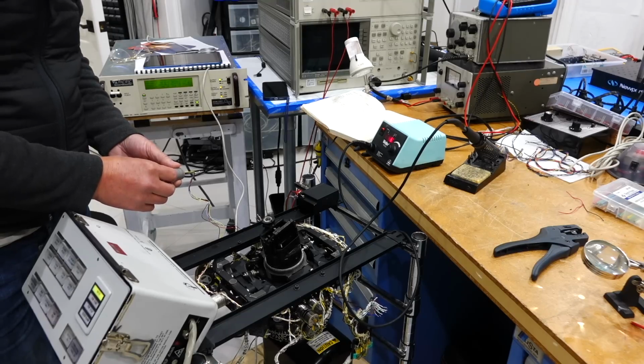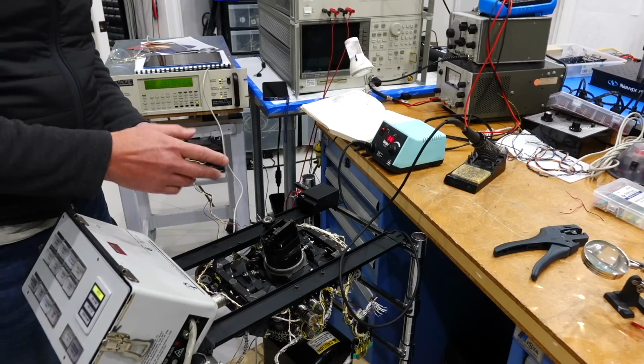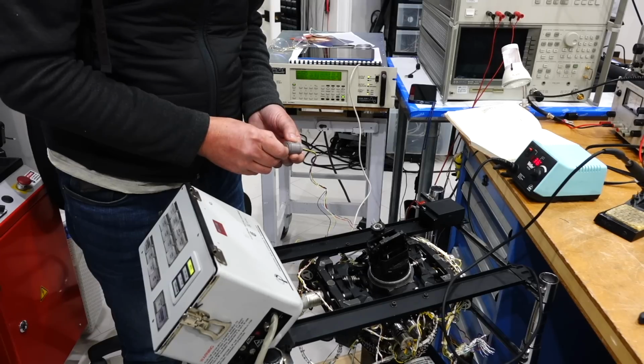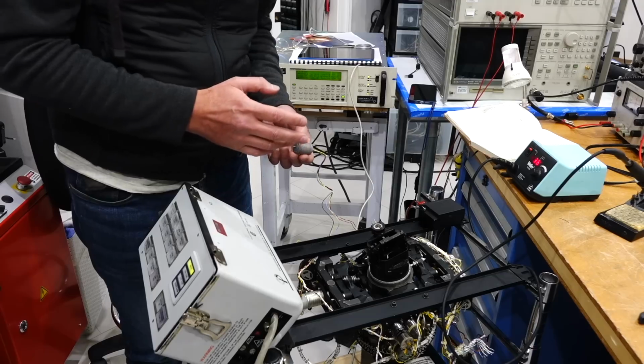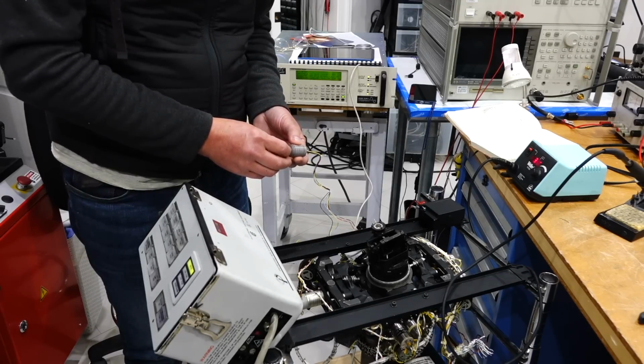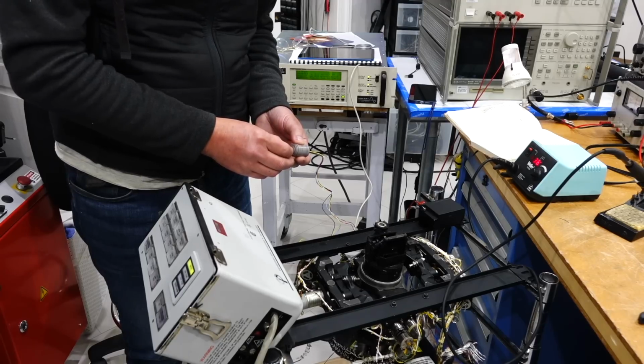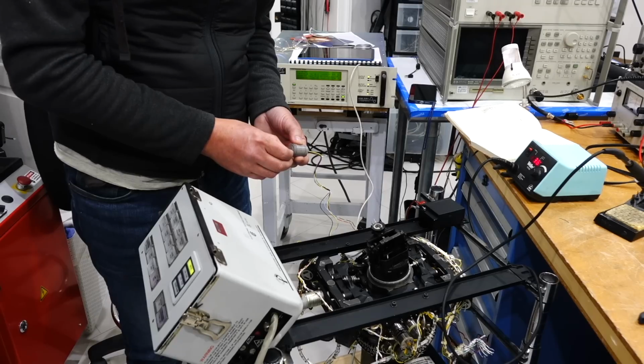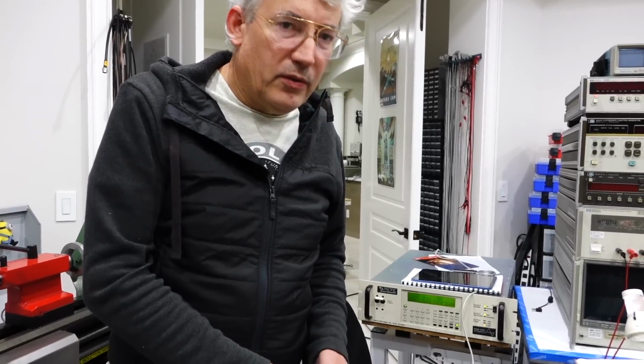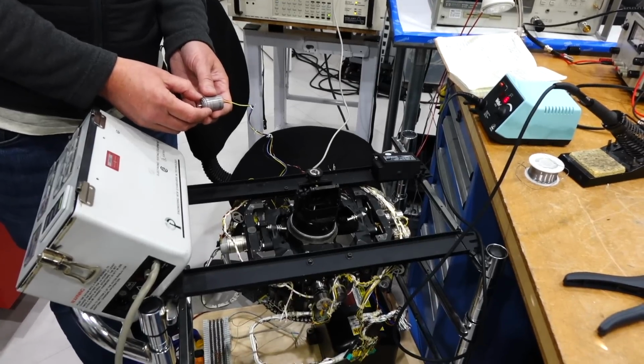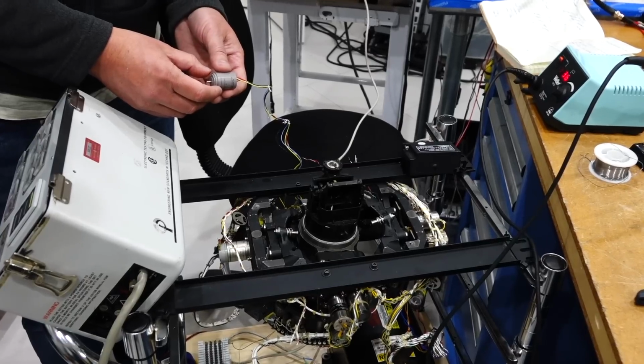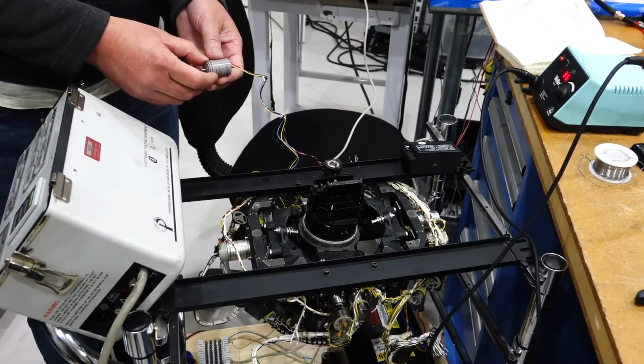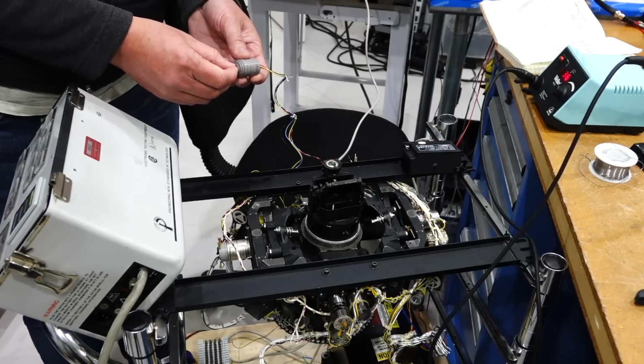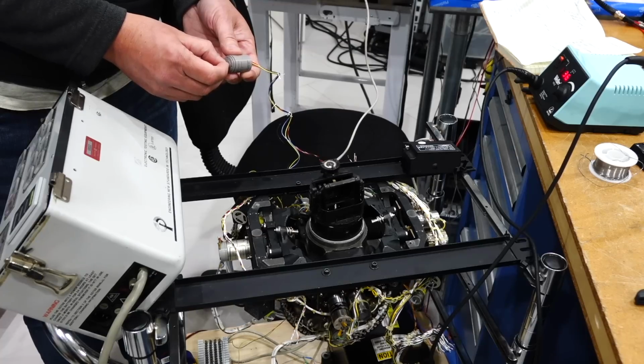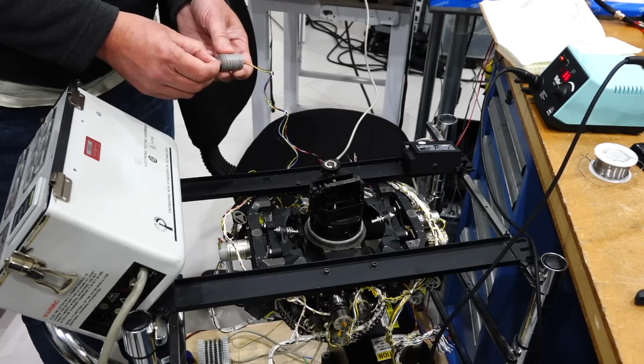So you added the rate transducer? Yes, somewhat at random. So maybe you still need to lower the gain. There's some progress at least. Yes, now it's dampening. Maybe I don't have enough rate feedback. Or it's wired in reverse? Oh yes, it's dampening out. Moments later: So you found out what wasn't working? Yes, the problem was that the phase of the motor was inverted. The reference coil, oh no, the other one. I inverted the phase of the control coil. So it was an anti-servo loop? Exactly, but somehow it still managed to stabilize itself. But now it stabilizes without any overshoot. Nice.